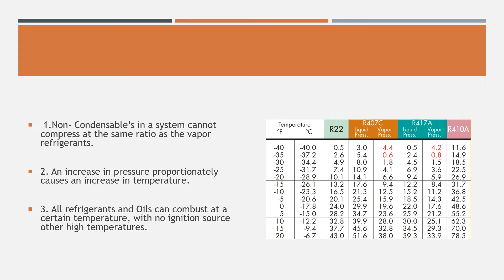Non-condensables cannot compress, creating an increase in temperature and pressure in the system. When refrigerant oils reach a maximum temperature, they can combust. If the non-condensables contain oxygen, the potential for an explosion is high.